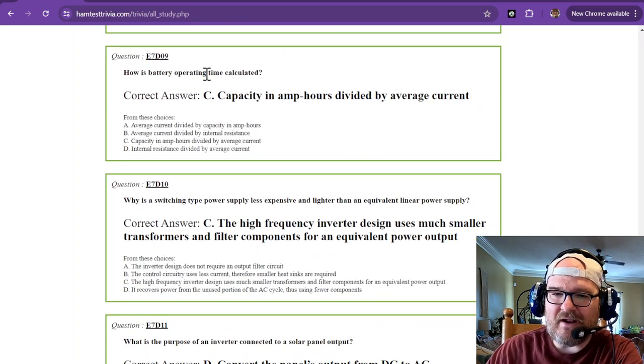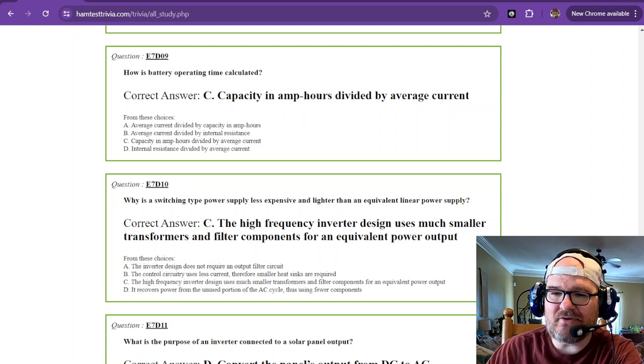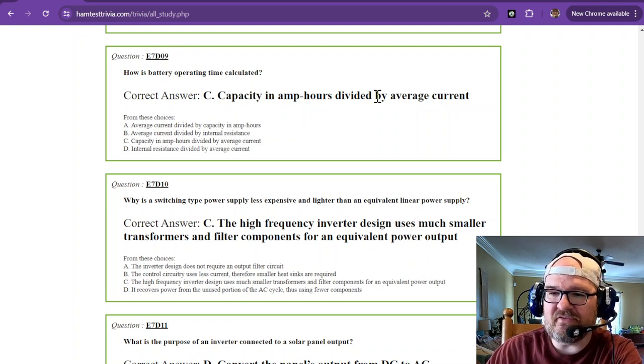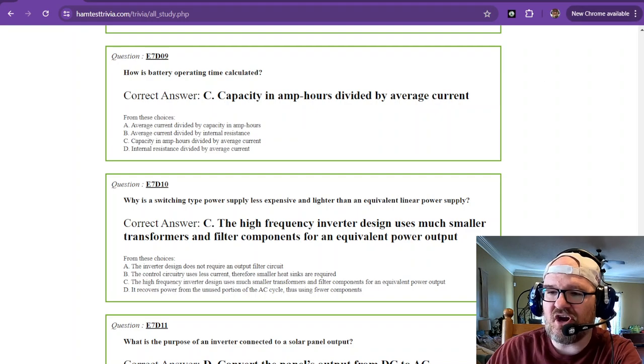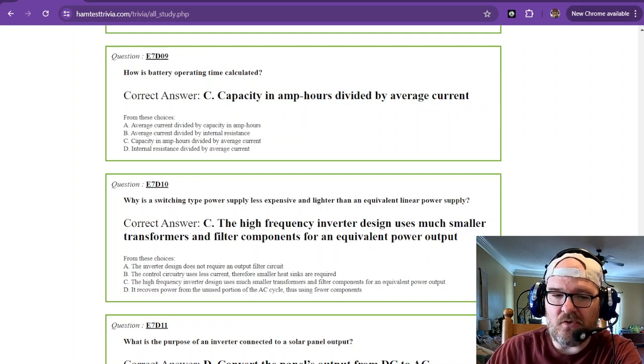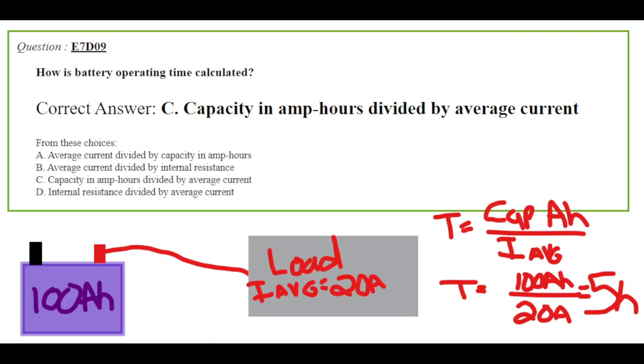How is battery operating time calculated? That is the capacity of your battery in amp hours divided by the average current of your load. So I've worked this out for you in wonderful picture in math. You can see the battery, it's 100 amp hours. Now ignore the fact that I didn't connect the ground or the negative, but you have 100 amp hour capacity battery. Your load averages 20 amps. So in order to figure it out, you take your capacity in amp hours. So you have a time there in amp hours, that's the time. That's the current. And they're put together for current time. And you divide that by your current average, which is in amps. Well, the amp divided by an amp cancels out. That leaves you with your time. So 100 amp hours divided by 20 amp load gives you approximately five hours of operating time.